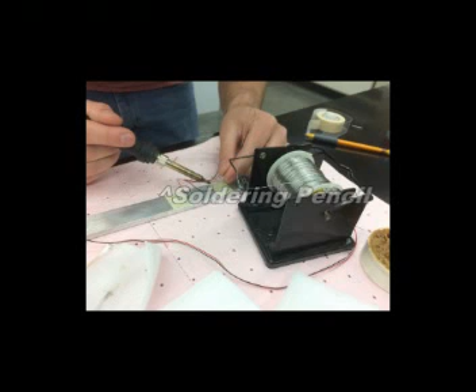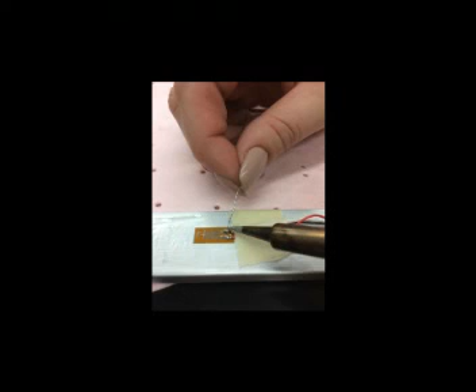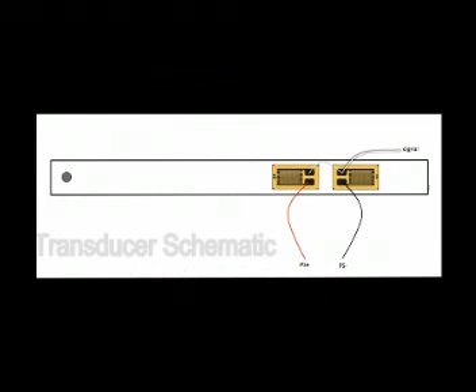1. Items to be soldered must be clean, free of oxidation, and free from adhesive or other films. 2. Join the wires to the gauge tabs using additional flux if necessary. Connections should form smooth, shiny fillets of solder without spikes or round lumps. 3. Inter-gauge wiring should be symmetrically arranged and of the same length from gauge to gauge.